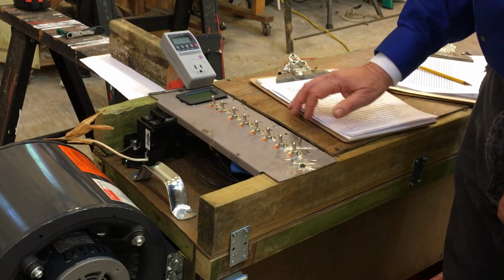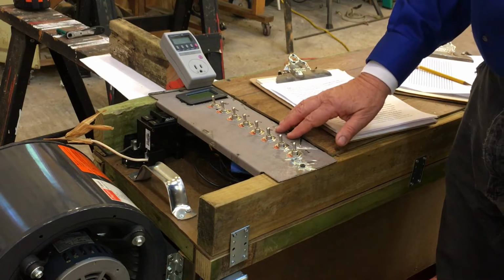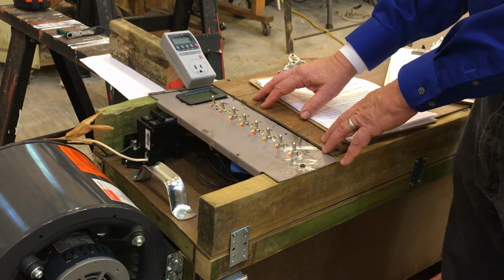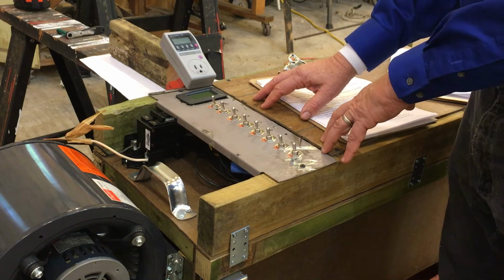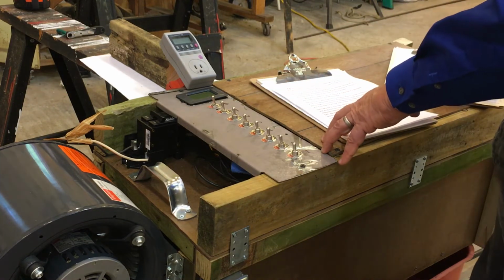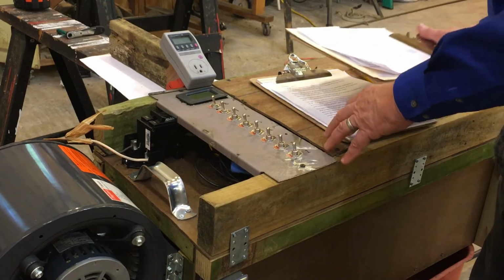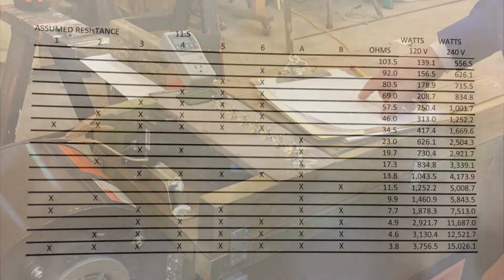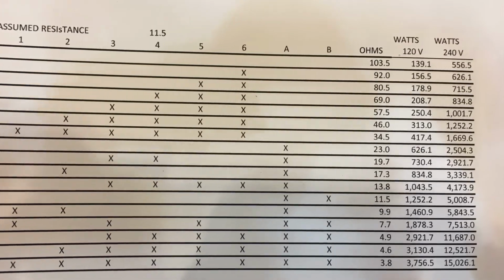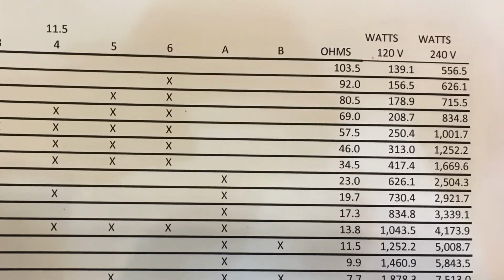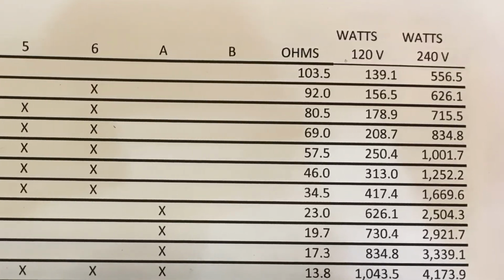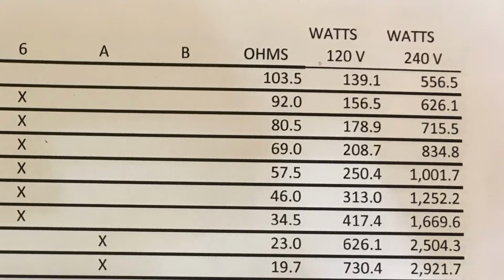The unit is equipped with these 8 switches, and by positioning these switches, I can select a resistance or an amount of load that's going into the generator. I reference a table that I have printed out here. The first column gives me the expected resistance for where the switches are set, and also the load in watts if it's 120 volts going into the unit, as is the case today, or what the load would be if 240 volts were being sent into the same terminal.